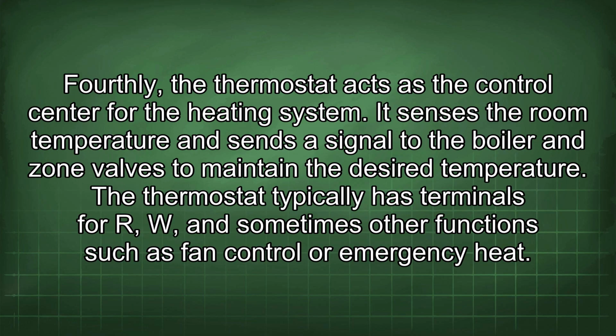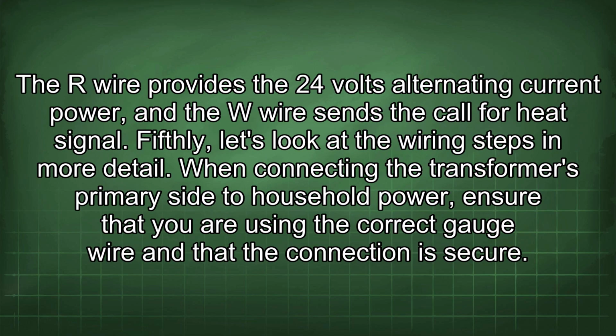Fourthly, the thermostat acts as the control center for the heating system. It senses the room temperature and sends a signal to the boiler and zone valves to maintain the desired temperature. The thermostat typically has terminals for R, W, and sometimes other functions such as fan control or emergency heat. The R wire provides the 24 volts alternating current power, and the W wire sends the call for heat signal. Fifthly, let's look at the wiring steps in more detail.